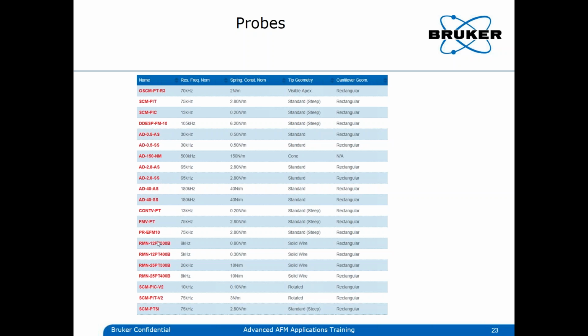And the other ones down here are full metal tips, like here a solid wire of platinum in this case, at various spring constants as well. These are made completely out of platinum, so there would not be a change for standard TUNA measurements in contact mode. Your metal will always be conductive. The only thing is you might see changes in the lateral resolution over time if you wear off the tip, but it's still conductive.